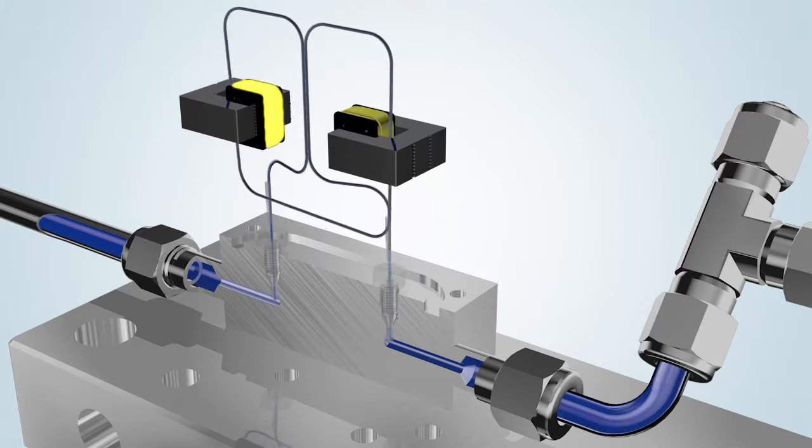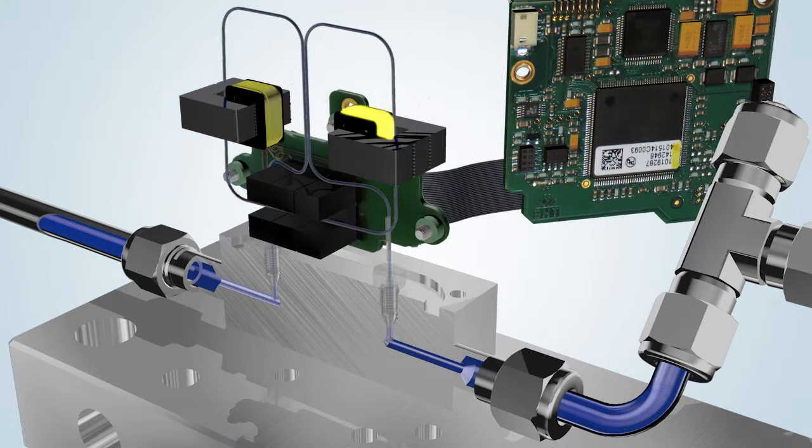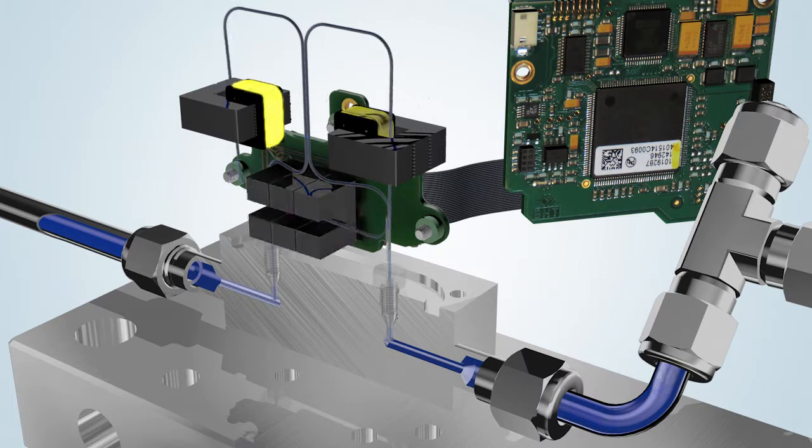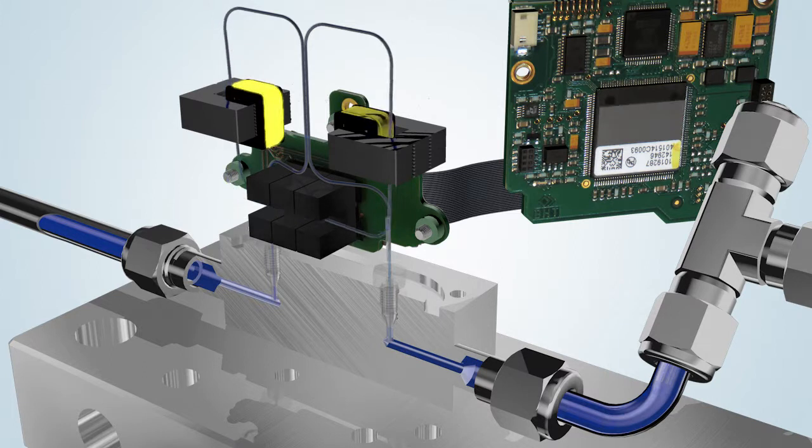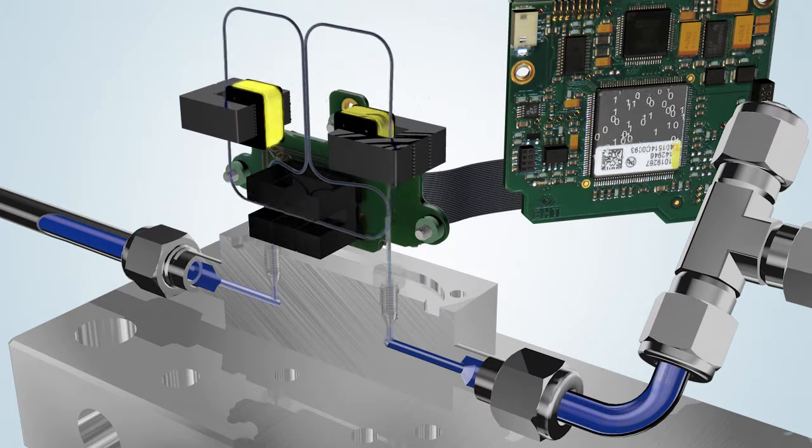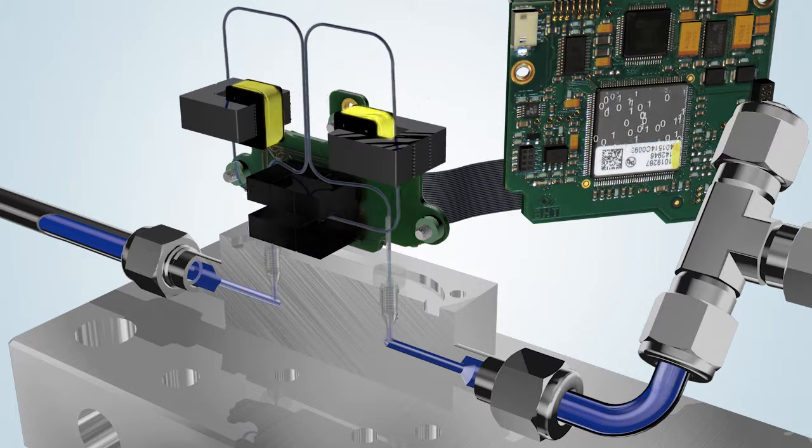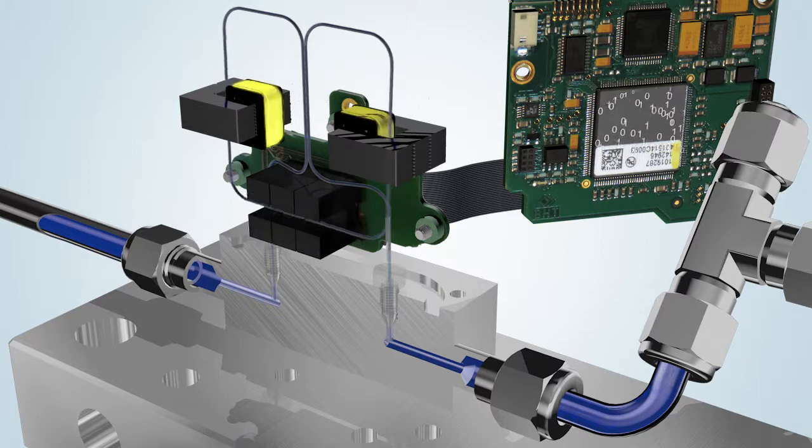The optical sensor precisely measures how much the vibration deviates. A signal is then transmitted to the digital electronics, which translate the measured vibrational value into a mass flow value, and compares this to the set point from a PC, PLC or analog port.